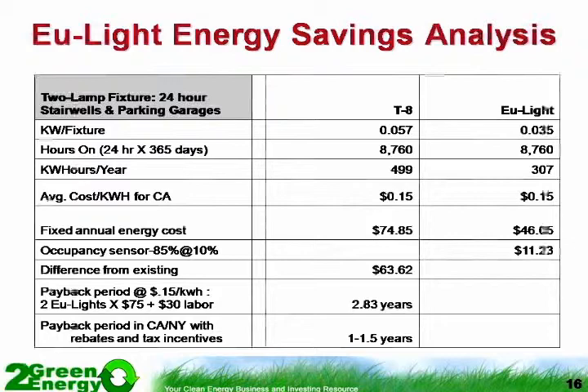So this was an example of what was required for stairwells and parking garages, and the use of being able to attach an occupancy sensor, assuming that 80–85% of the time nobody was there. But due to code requirements, there had to be a minimum amount of light—when someone walks by, it's on 100%, and when someone's not there, it's at 10%.